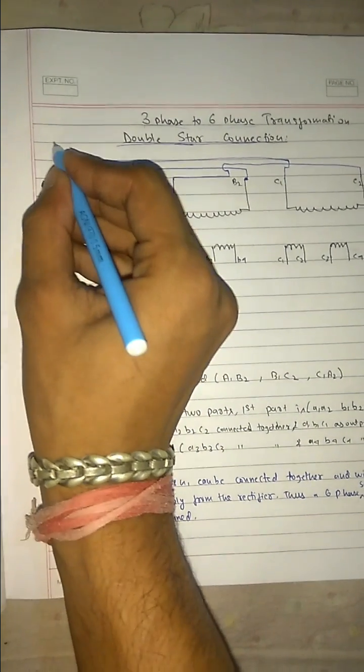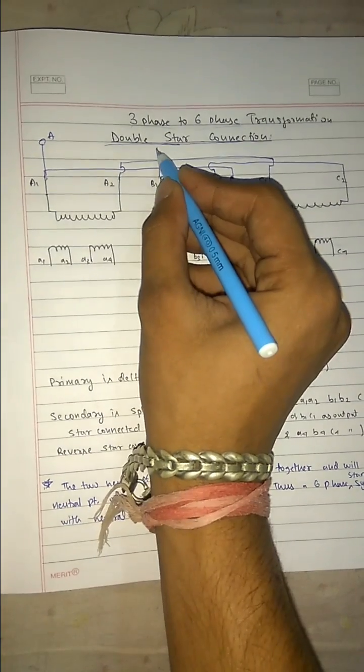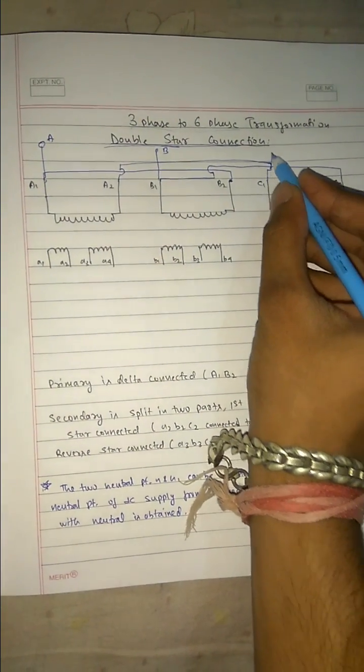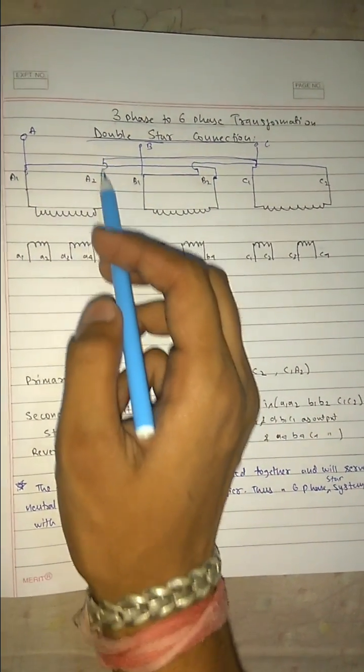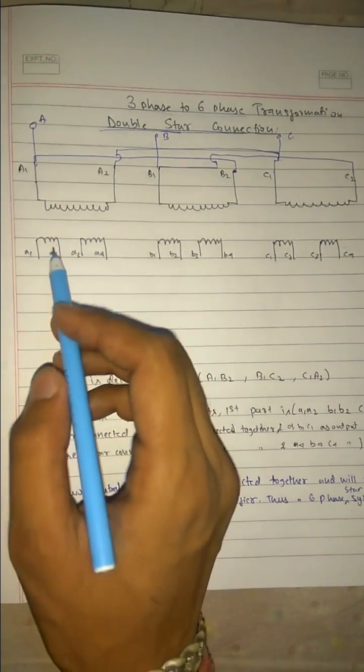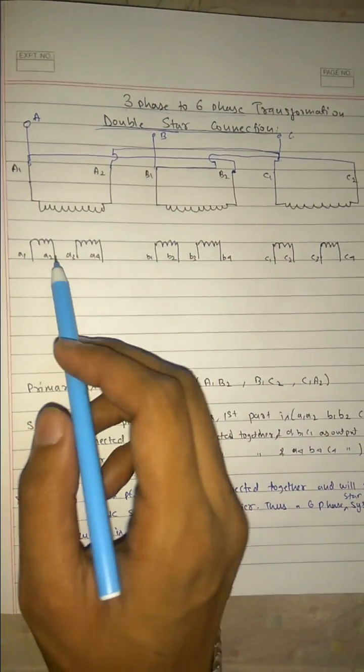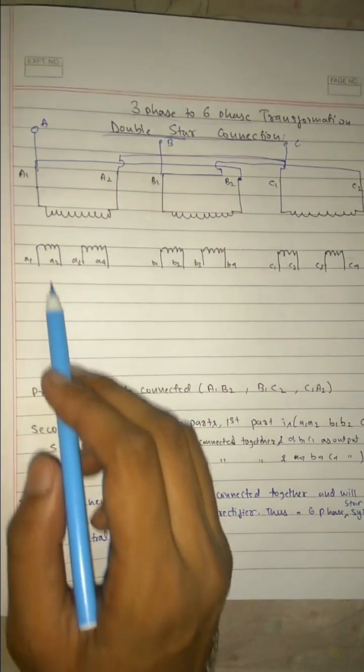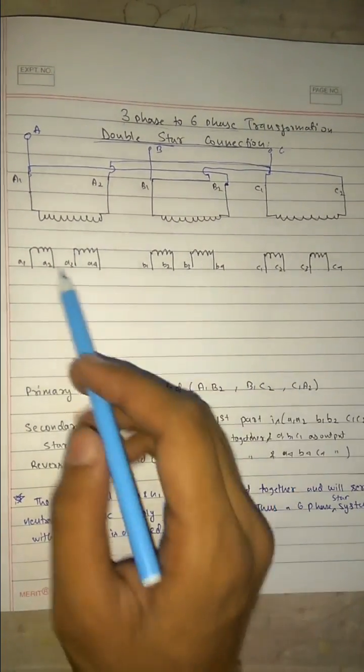And these are our inputs a, b, and c. So our primary is delta connected now: a1-b2, b1-c2, and c1-a2. Now it's time for the secondary. It's split into 2 parts as you can see. Now here again, for easy connections, remember first we take these 3 things: a1-a2, b1-b2, and c1-c2.